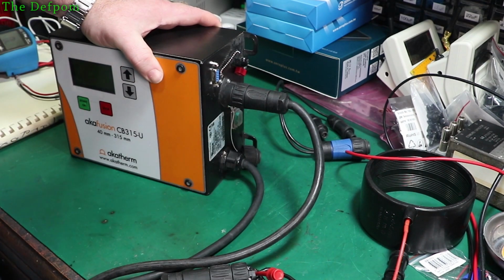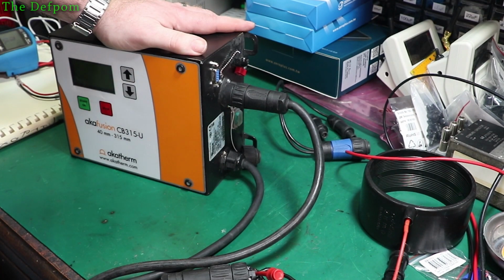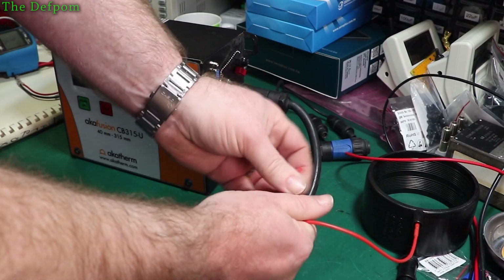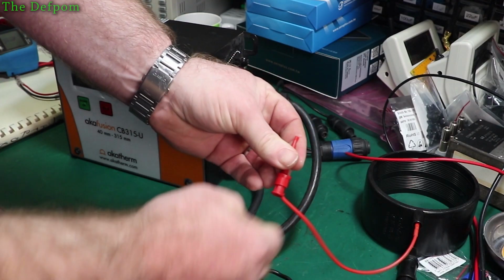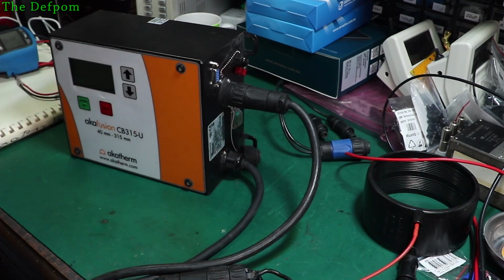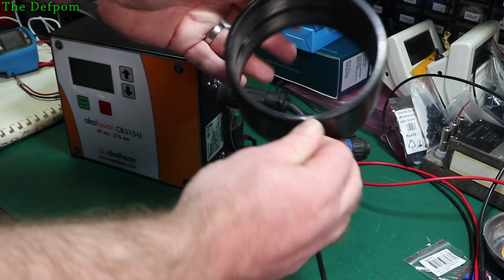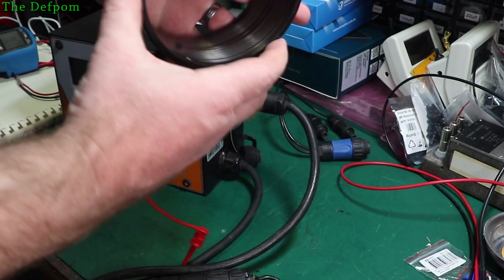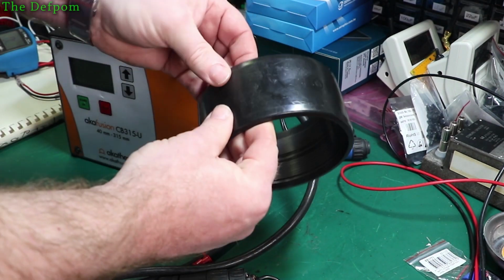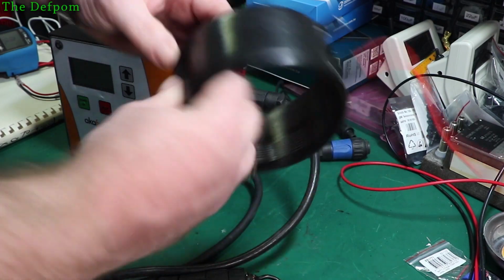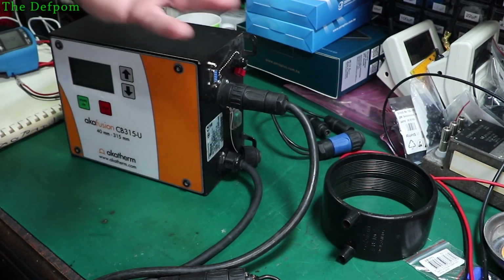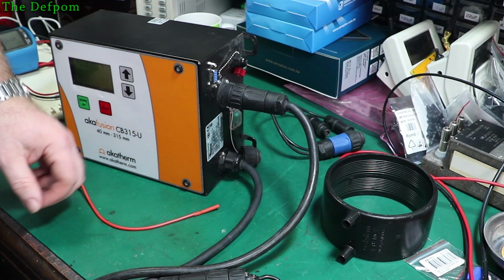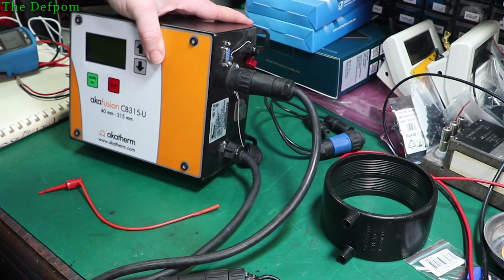So it's still got that error message coming up on the screen saying about needing servicing. Yep, it's barely warm, right? So it did put a little bit of current through it, but not enough for a long enough time to actually cause a problem. Alright, and unplug that. Yeah, there's no warmth in that. Didn't get anywhere near it, so that's good. But this is why I wanted one of these fittings, so I can actually test and verify what's going on. So yes, dodgy cable.